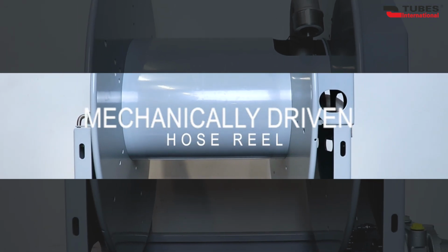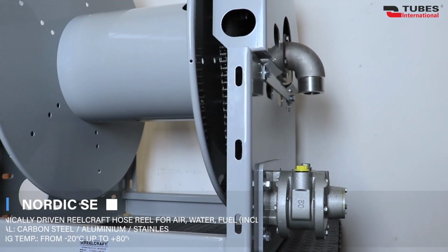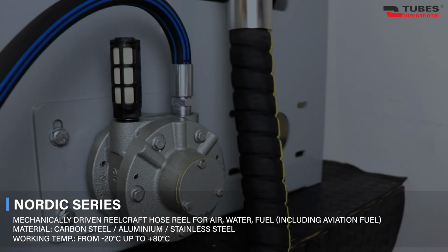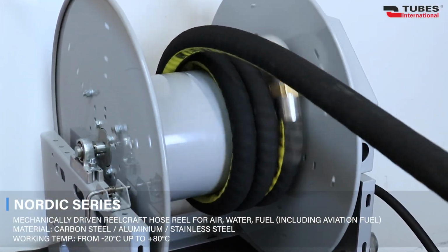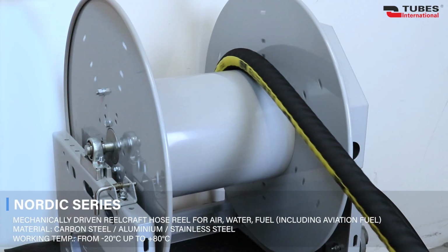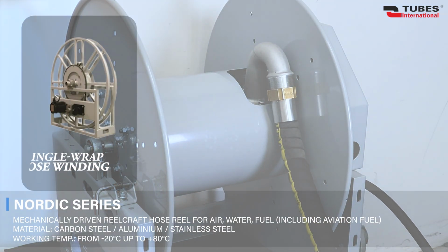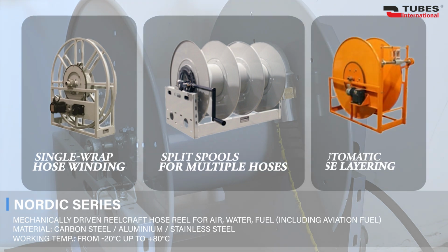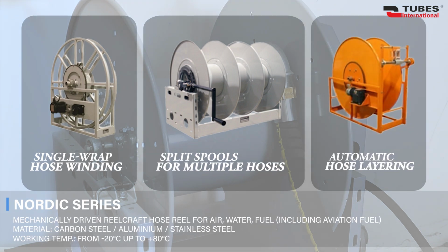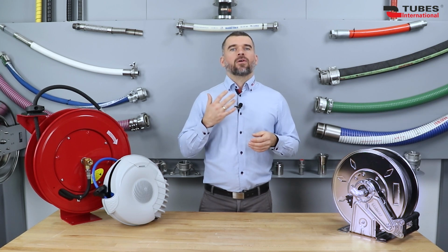Mechanically driven reels. The hose is unwound and rewound automatically using a motor powered by pneumatic, hydraulic, or electric drive. Here we highlight the Nordic series as an example. It's worth mentioning additional options available for this series, such as single wrap hose winding, split spools for multiple hoses, automatic hose layering. These reels are designed to handle longer and heavier hoses with larger diameters, up to 4 inches, which would be impossible to rewind manually. They are an ideal choice for industrial applications and help increase productivity by saving time. They are widely used in the offshore industry, steel mills, and airports.